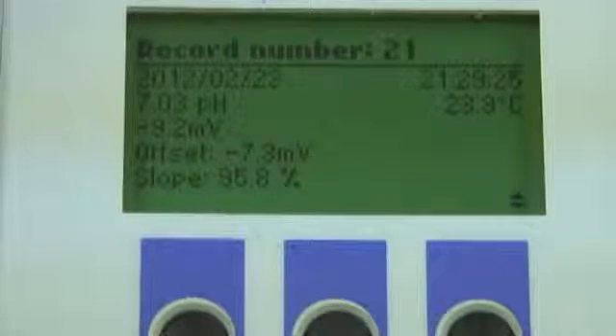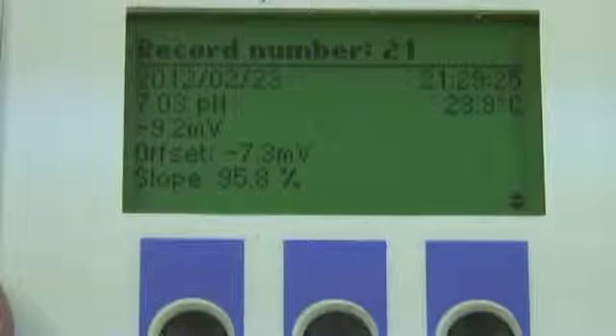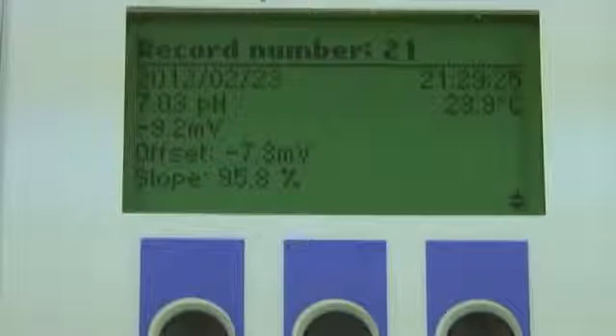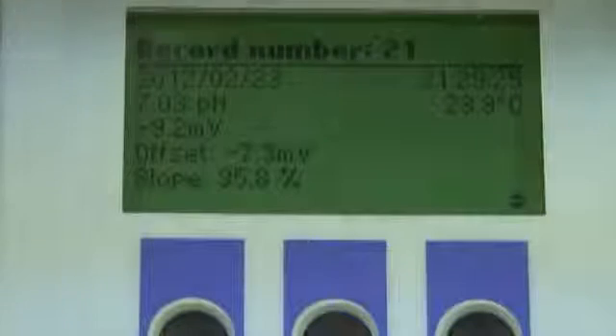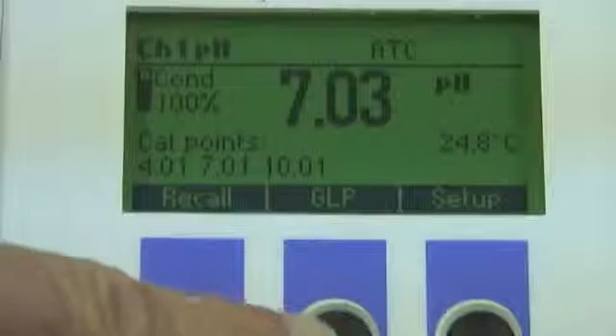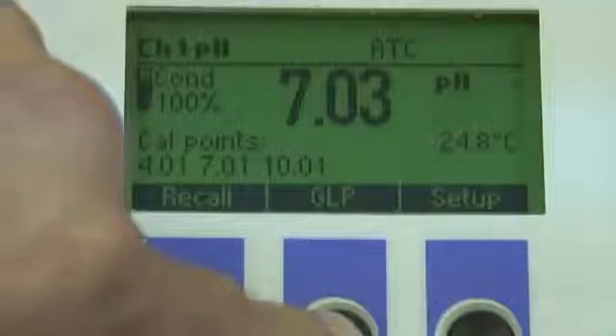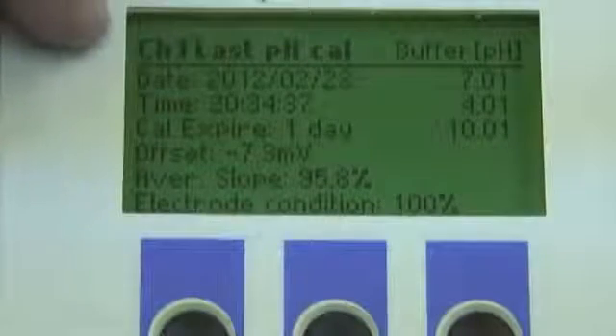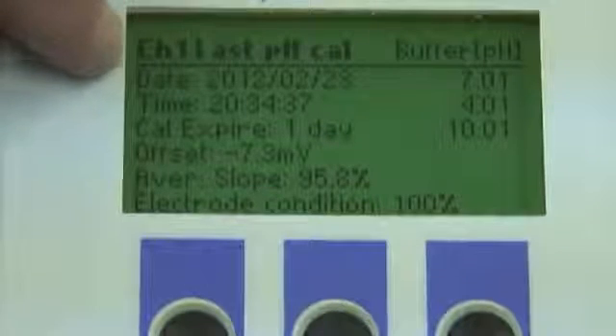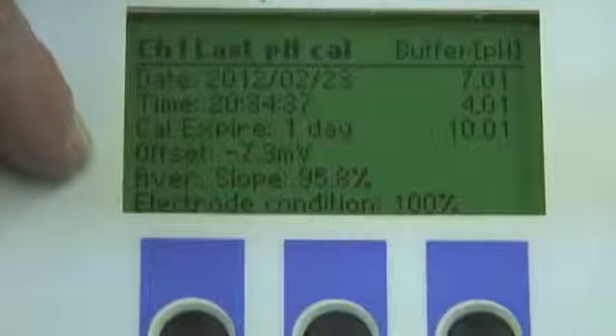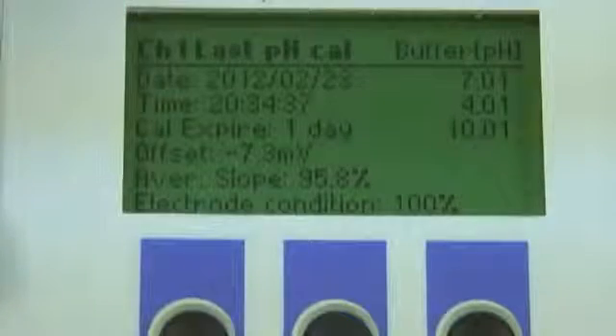and the slope. Now, if you want to download this information to your PC, remember we talked about the fact that this has a USB connection port in the back, and you simply connect the meter to your PC and download the data. Let's escape out of this and take a look at GLP, which stands for Good Lab Practices. And this is information based on the last time that the probe was calibrated. So here we see the date, the time, the offset, the slope, and the buffers that were used.